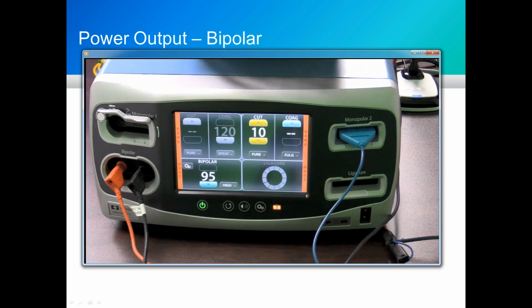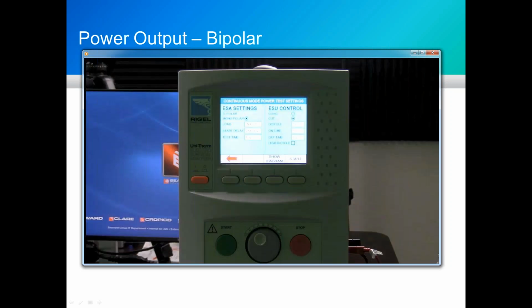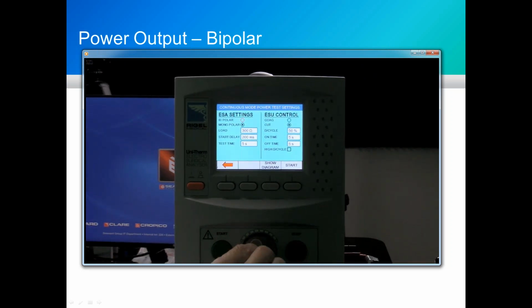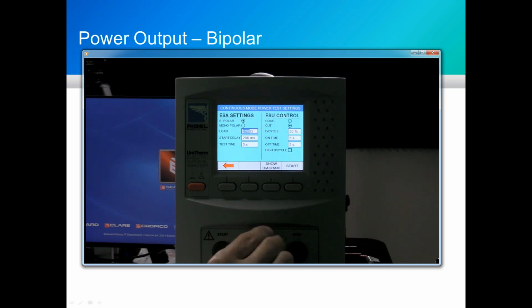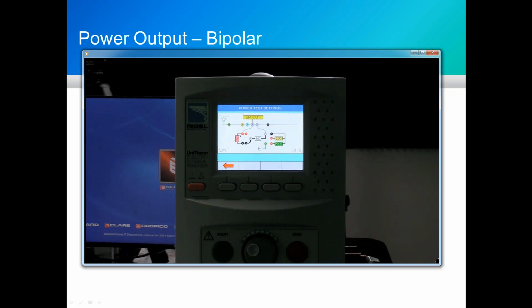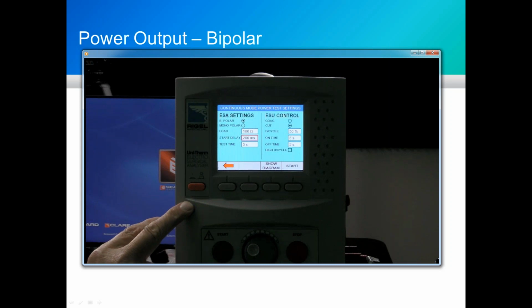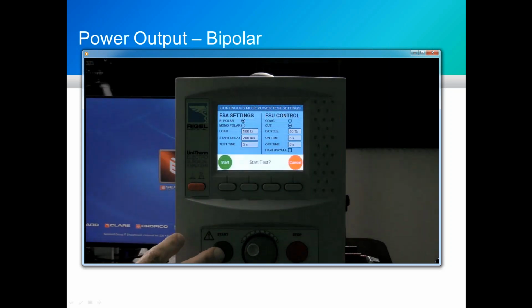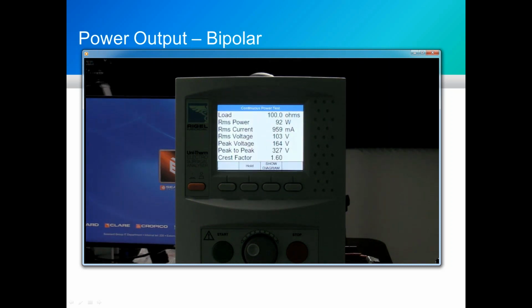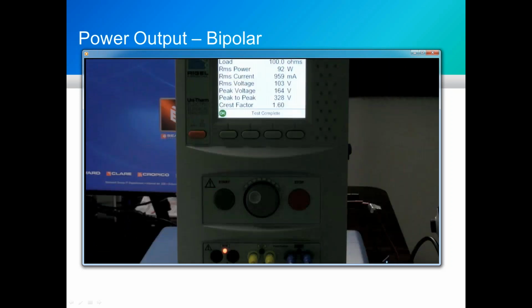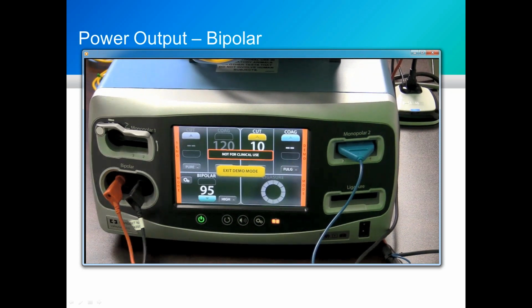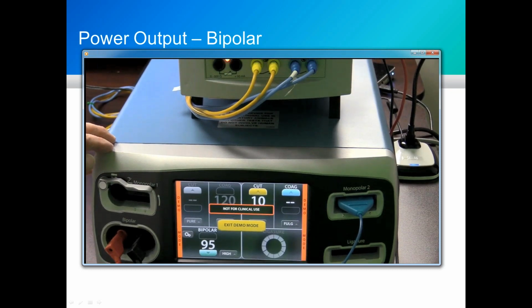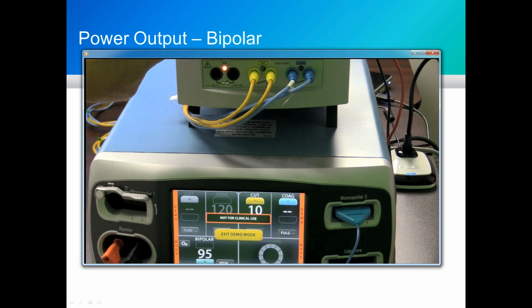I'm going to test at maximum power. I'm going to set it for bipolar, set my load resistance to 100 ohms. So we measured 959 milliamps, 92 watts is the power calculation. The FT10 has a tolerance on power as well, but again, the pass-fail is done on current.